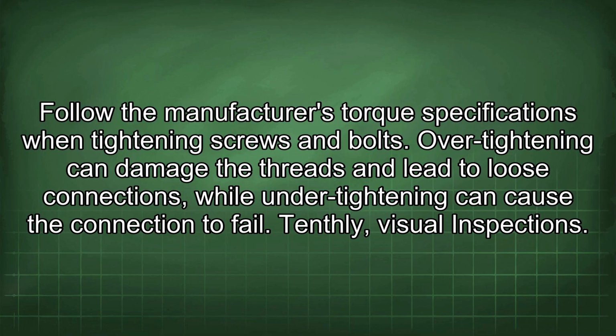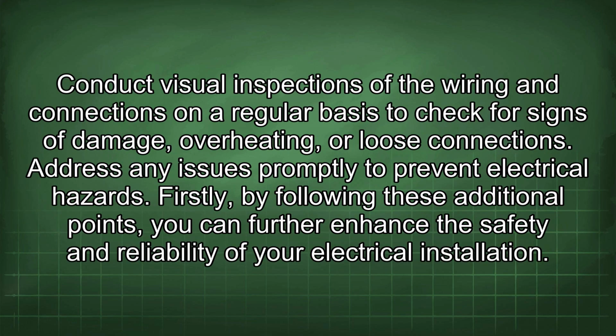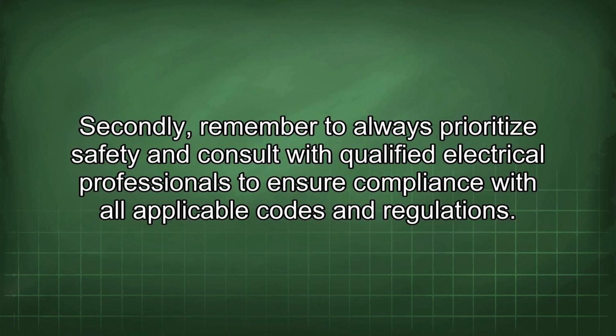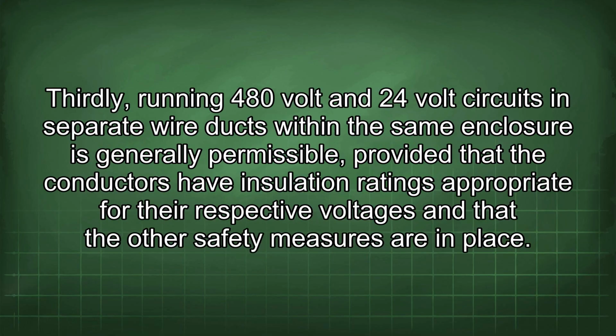Tenthly, visual inspections. Conduct visual inspections of the wiring and connections on a regular basis to check for signs of damage, overheating, or loose connections. Address any issues promptly to prevent electrical hazards. Firstly, by following these additional points, you can further enhance the safety and reliability of your electrical installation. Secondly, remember to always prioritize safety and consult with qualified electrical professionals to ensure compliance with all applicable codes and regulations. Thirdly, running 480-volt and 24-volt circuits in separate wire ducts within the same enclosure is generally permissible, provided that the conductors have insulation ratings appropriate for their respective voltages and that the other safety measures are in place.